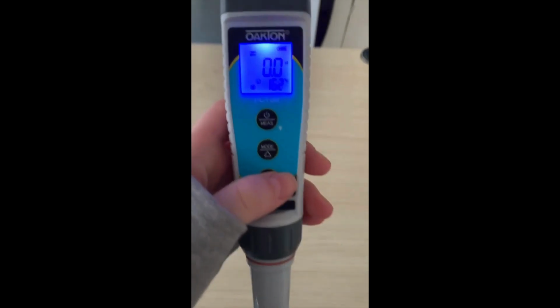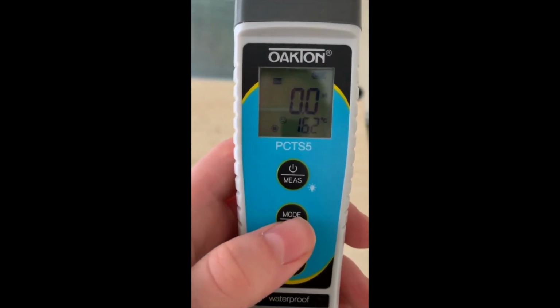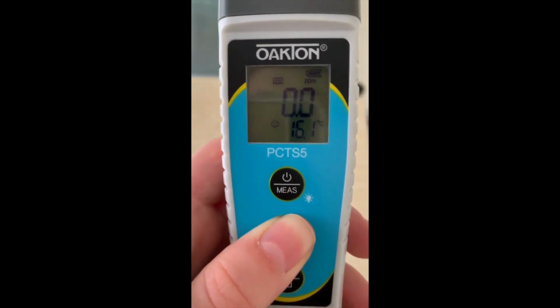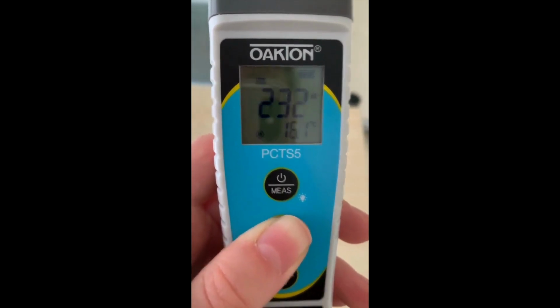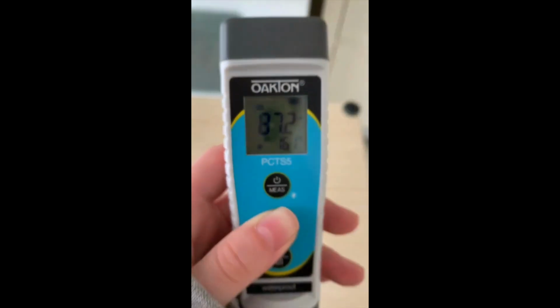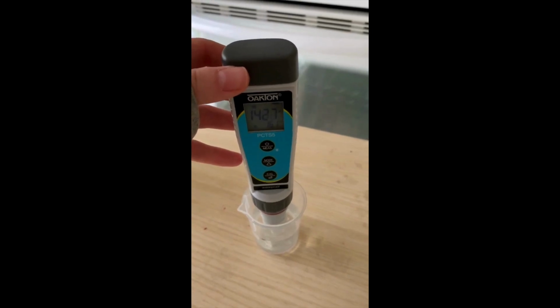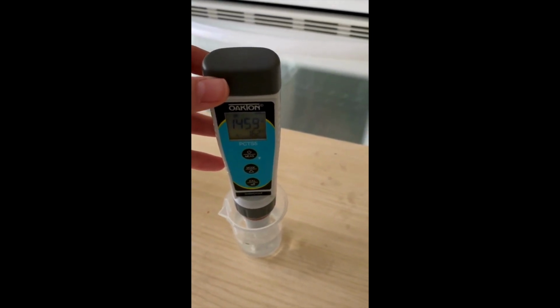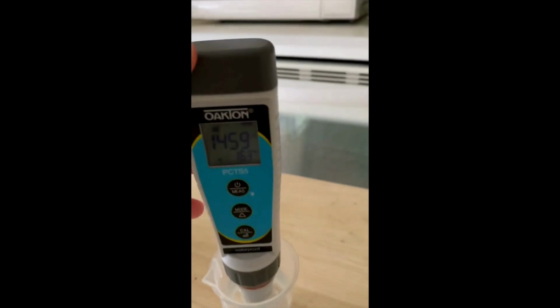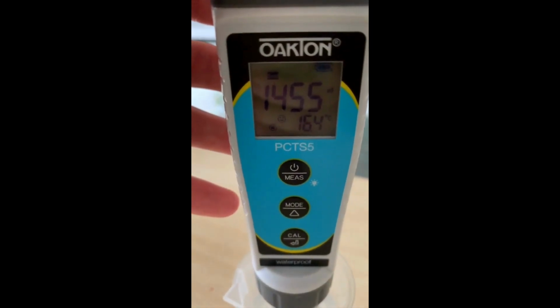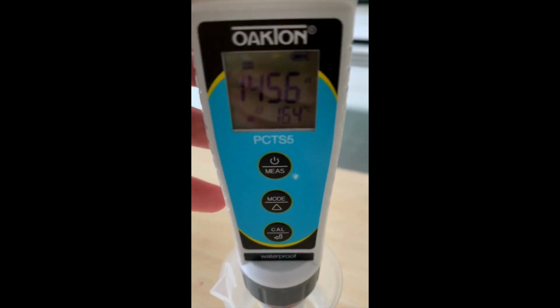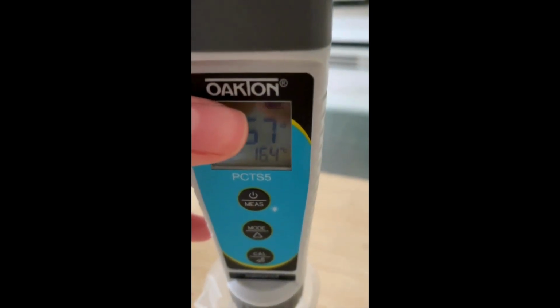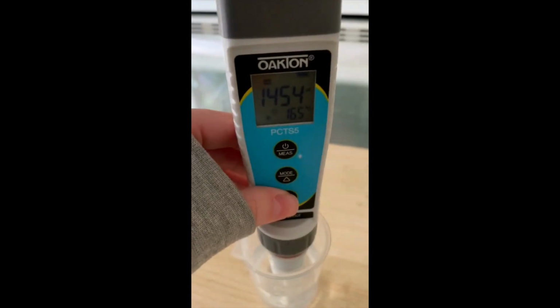And then we're just going to hit mode to make sure it says conductivity. It already does, but just in case it didn't, you would just hit mode until it says conductivity right there at the top. And then what you're going to do is just place the probe into this solution right here, the conductivity solution. And you're just going to wait for it to stabilize. And that's when the smiley face comes up, so you can see it's stabilized right now. And then once it's stabilized, you're going to long press on cal.